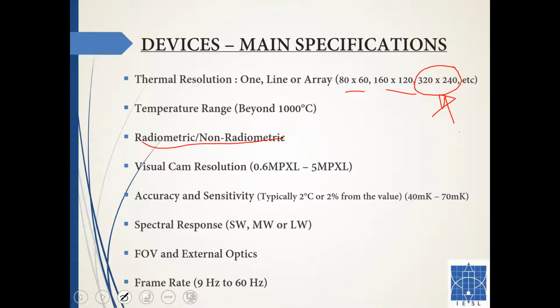This is really interesting—this is where price points vary a lot. Radiometric versus non-radiometric specification has a price difference of about $500 US. Radiometric means that when you have, say, an 80 by 60 imager, you have a total of 4,800 points on the thermal imager. So when recording a photograph through this imager, you get distinct readings at all 4,800 points when you capture the image.